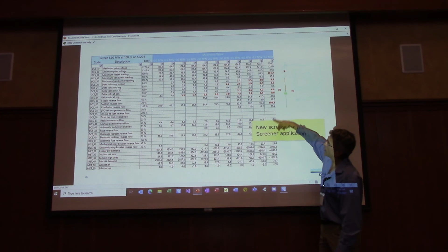As the generation is increased, these are all the types of things we're looking at: delta voltage, loading, all these different sorts of potential problems. When we hit a screen limit, the number turns red. So at 1 megawatt, we've got a problem with delta volts all trip, meaning if all the generators were to trip at once, we'd have more than the 5 volts we allow for voltage flicker.